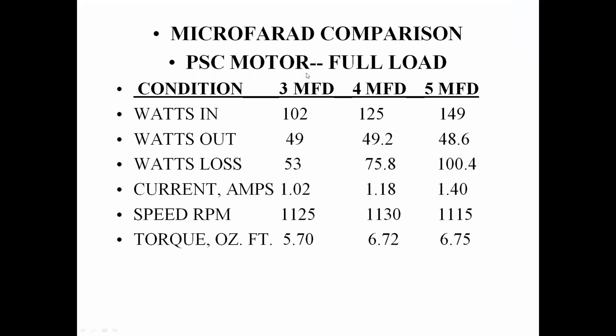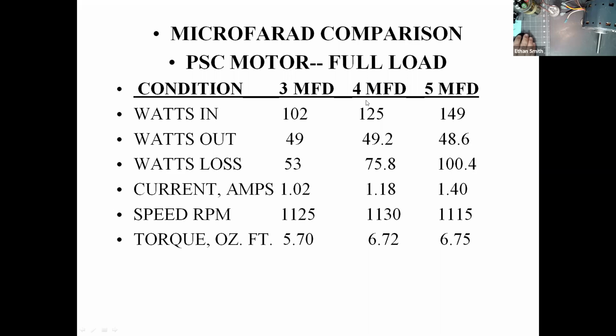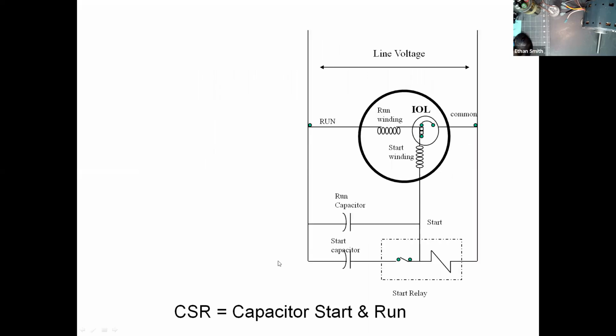In this case, this is a 115 volt motor, so it's got a single phase of power, and then we're creating a second phase of power by offsetting it with a capacitor. So we get that extra starting torque there, and we lose a little bit in efficiency. So we're balancing those two, and that's our sweet spot, because when we went to a 5, we didn't really gain anything on our torque, but we lost a lot of efficiency. Okay, so that would be a permanent split capacitor.